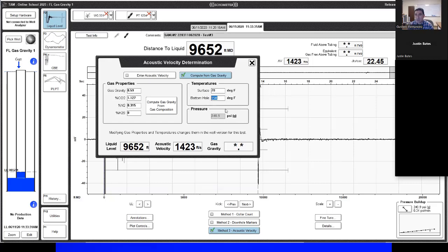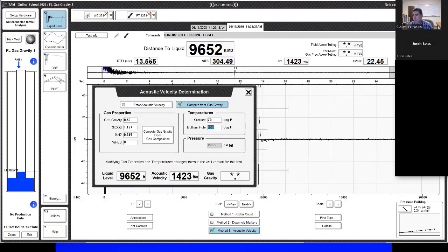So we have enough information now to calculate the acoustic velocity. The software knows 1423 is coming from the gas composition, and the time to the liquid level. Now we have enough information to calculate distance to liquid. It's important to have a good gas composition value.